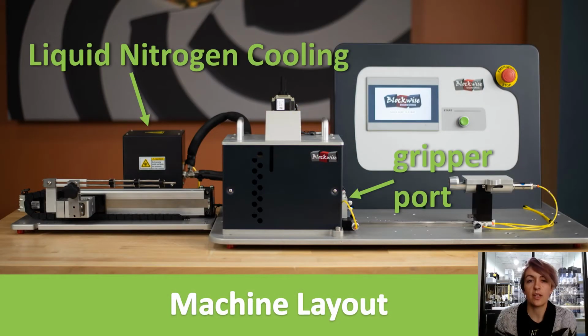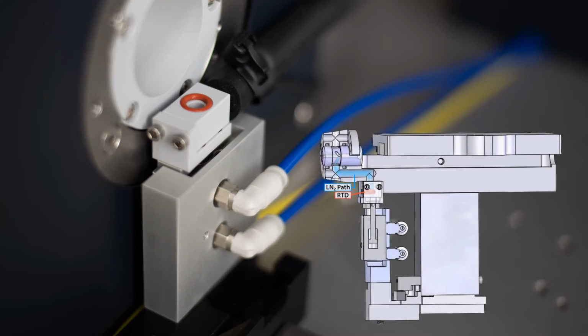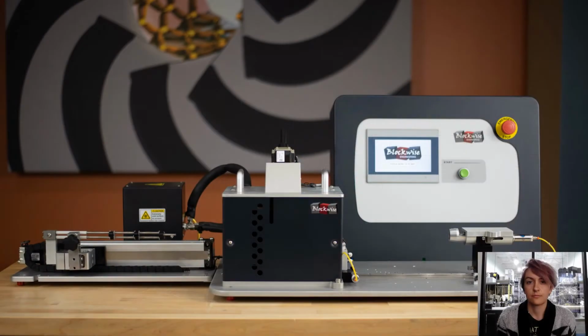Lastly, the LX also has an available liquid nitrogen cooling option. There's two configurations for this option, and the most common, the one that you see here in this picture, is the catheter cooling option. This option will direct a stream of liquid nitrogen onto the stent just before it's pushed into the catheter. The purpose of cooling is to maintain the compressed state of the stent during the loading process in order to try to reduce friction. So that's it for the general layout of the machine and the options that are available, but now let's get into some specifics about these components.